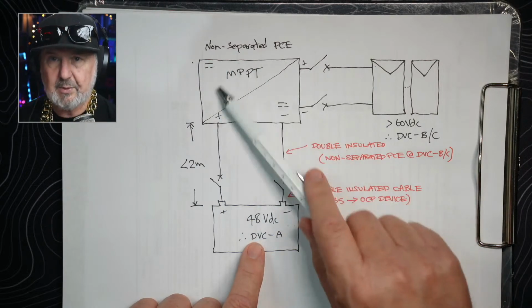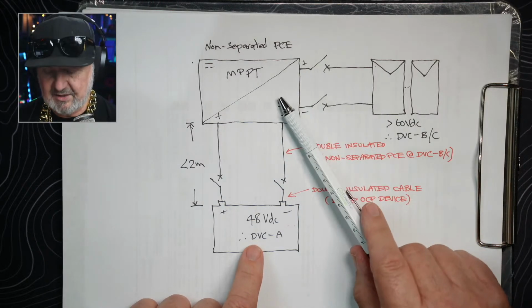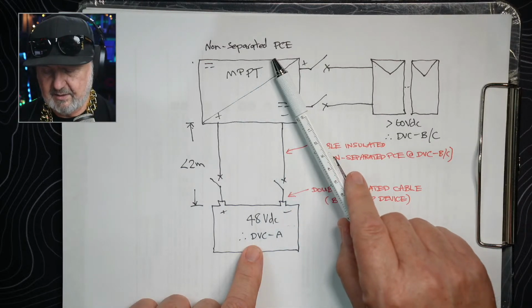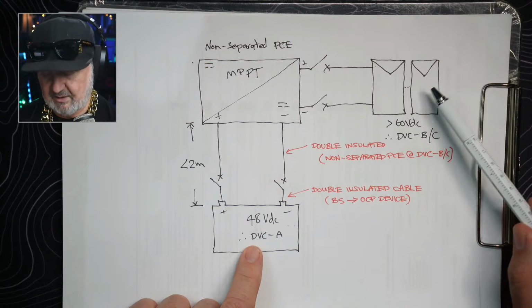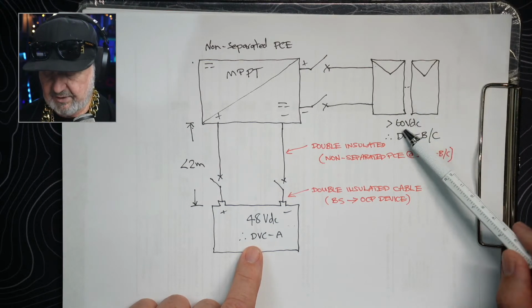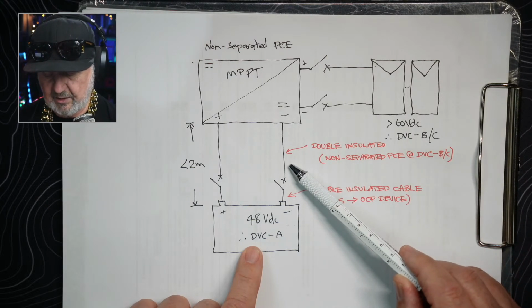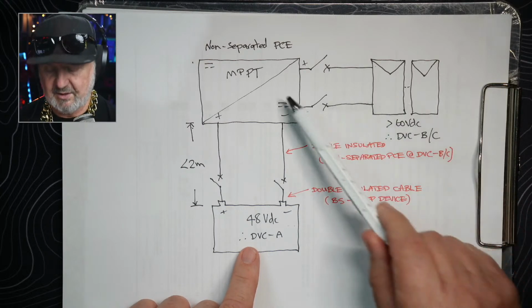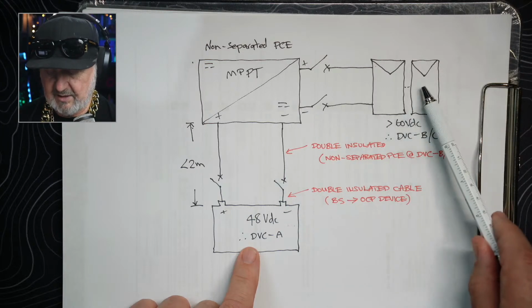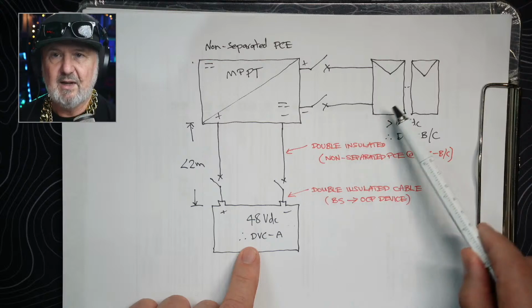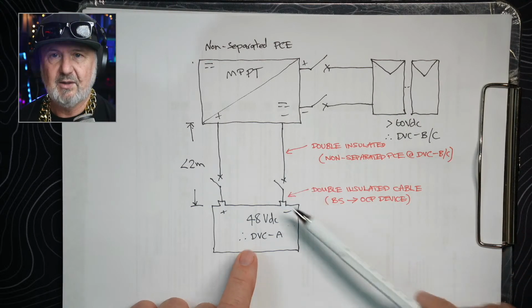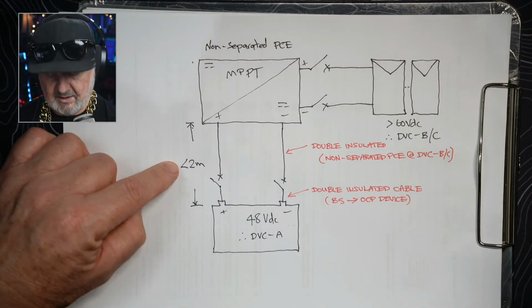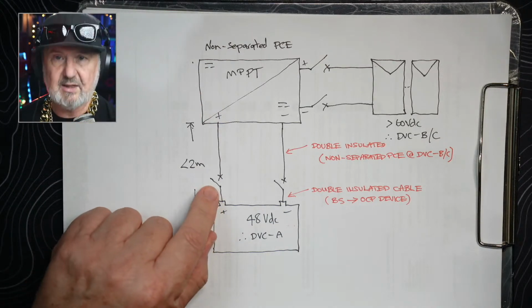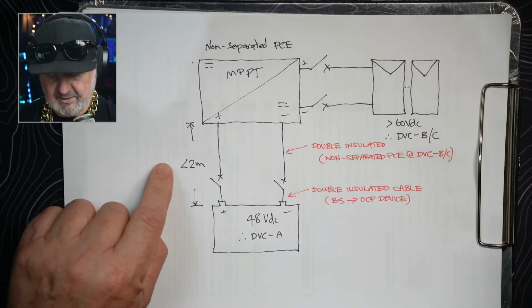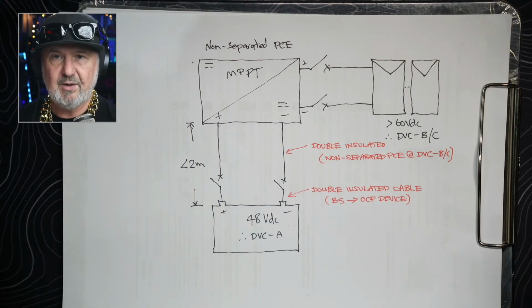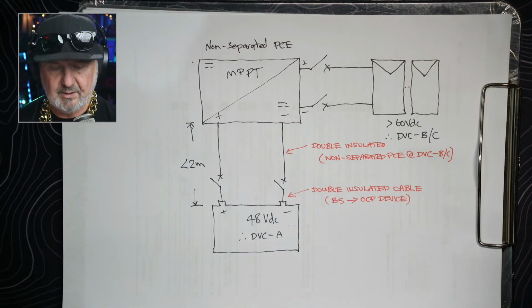Now, if the MPPT, in this case, or more technically the PCE, is not galvanically isolated, therefore it's non-separated, and the highest voltage present, which is likely to be the PV array in this case, is over 60 volts, then this cable needs to be double insulated as well. The concept there is that because there isn't galvanic isolation between the PV side and the battery side, you can actually have the PV voltage under fault conditions appear on this cable. So I've also shown the 2 meter rule here. As long as there's less than 2 meters between the PCE and the battery, we only need 1 point of isolation at the battery system. But if it's greater than 2 meters, we're going to need isolation at both the PCE and at the battery. So that 2 meter rule kicks in.